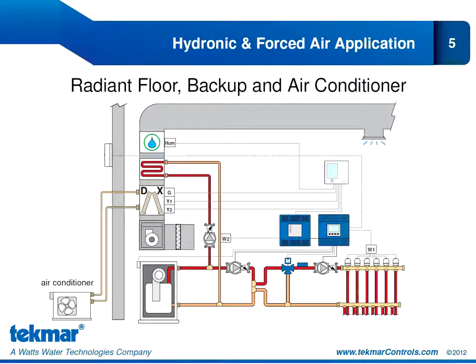Our second non-heat pump application is another very common application where we're using a hydronic system for heating and an air conditioner for cooling. In heating mode, our first stage of heat is provided by the radiant floor. Our second stage of heat is operated with the fan coil through the W2 relay connection. When we're in cooling mode, our air conditioner can provide 2 stages of cooling with the Y1 and the Y2 relay connections. Again, we're also controlling the fan and humidification through the accessory relay. So this is a 2-stage heat, 2-stage cool application.